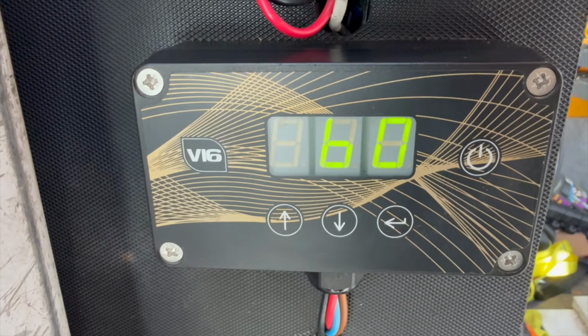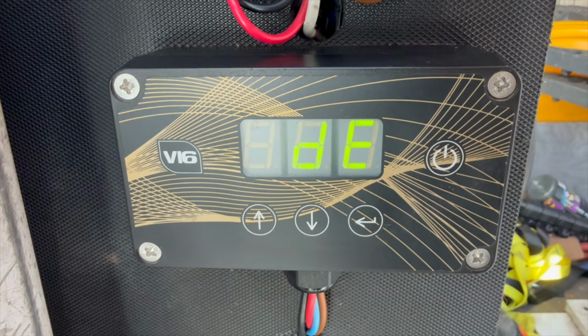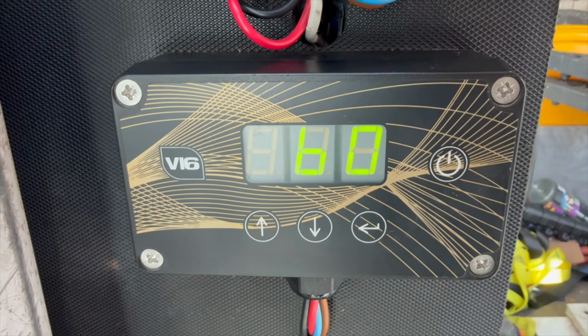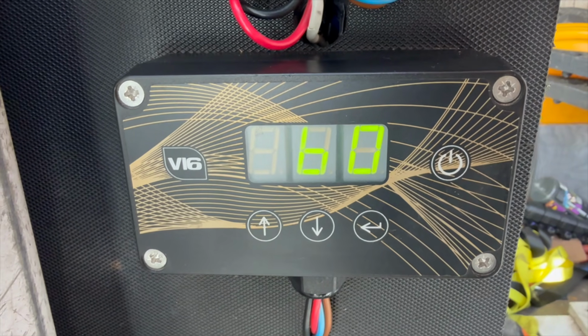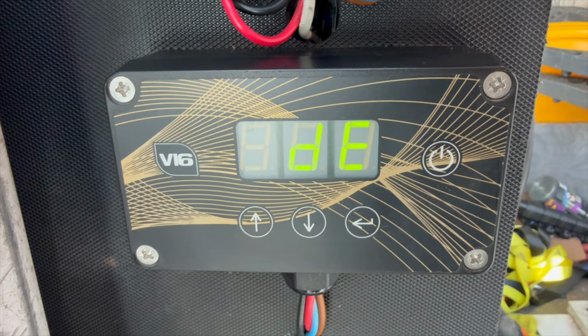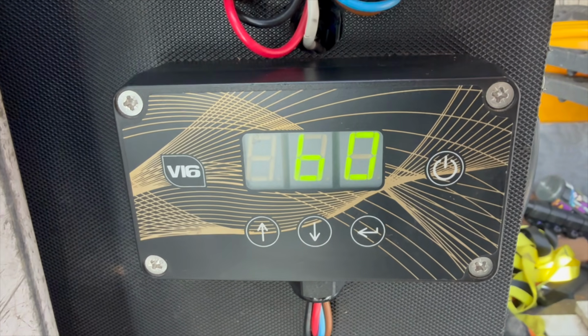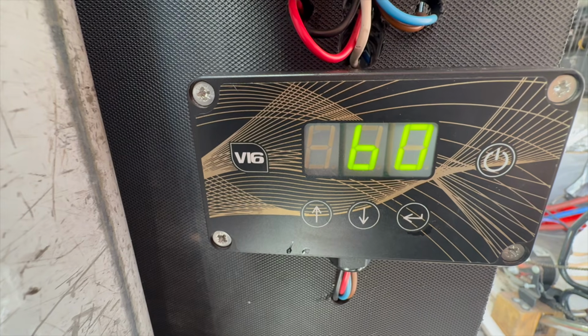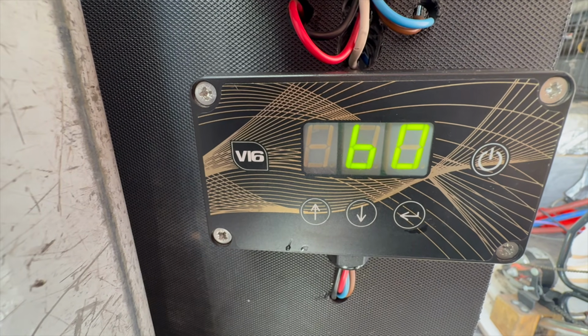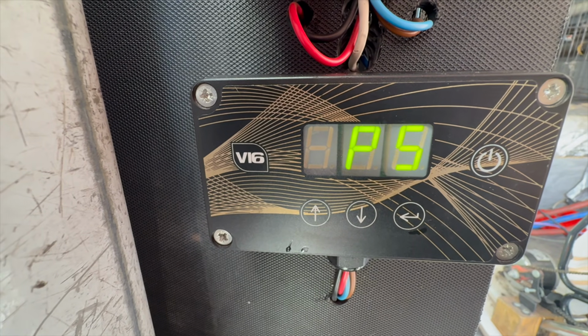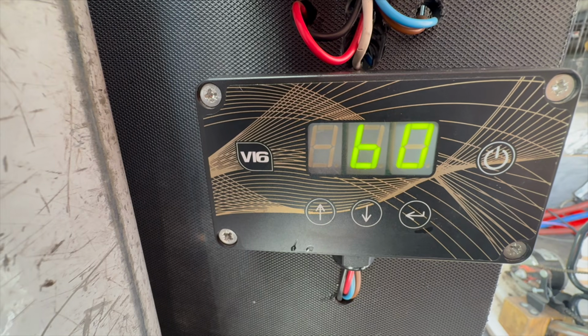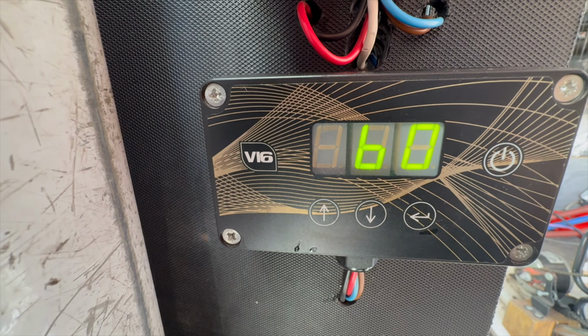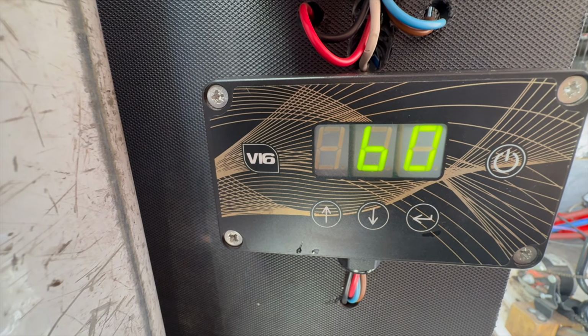Very often people will see DE, dead end, come up unexpectedly. They're working away on a building, suddenly there's no water, and they think, what's going on? Walk back to the van and they see DE. The other one people will often see is what is referred to as P5. Actually it's PS, the pressure switch. I'm happy with either. When it works, it works. And so we're going to see the pump stop, water flow stop, and it may be the first time people have seen one of those two messages.